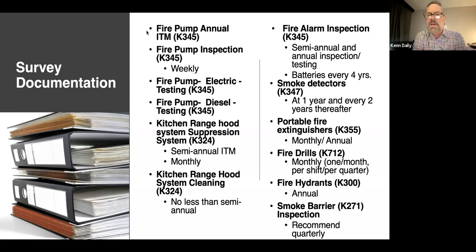No less than every 6 months, removing all that grease-laden vapors or grease that has attached itself to the metal. And then you have fire alarm, K-tag 345. Actually, it starts at really KTEG 341, but I see mostly 345 used as a citation for semi-annual and the annual functional test. You also frequently have your sensitivity testing, most of this is every 2 years at this point. And so you have to have that detector sensitivity done. And I said the semi-annual test has been the test that has gotten most of us in trouble or not having done. Annual fire extinguisher PM, and then of course your monthly check off of the devices is the next thing.